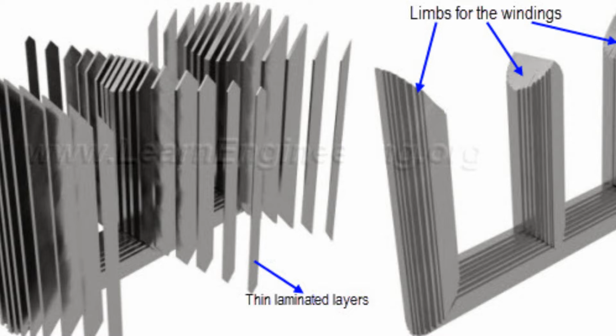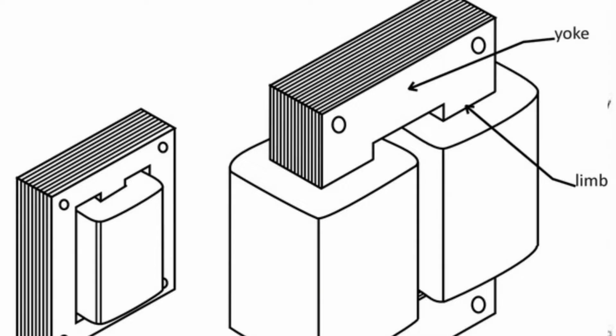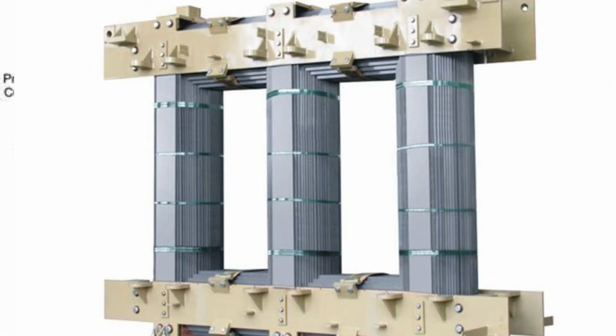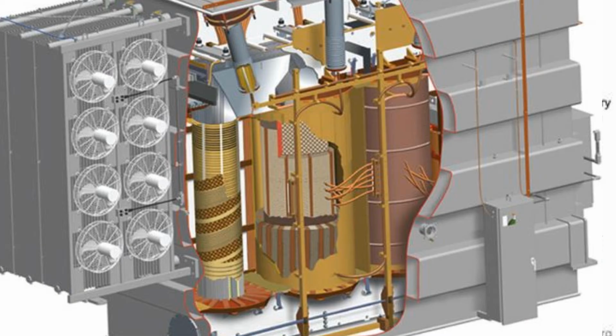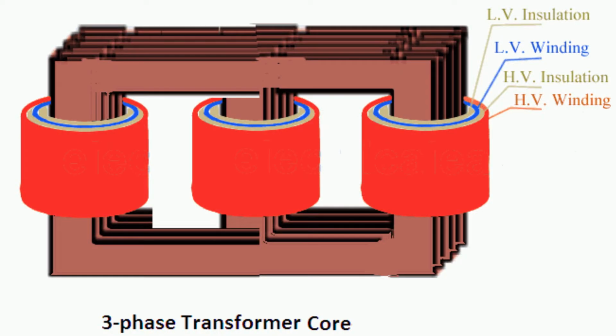The vertical sections of the core in which the windings are carried are referred to as the limbs, while the horizontal sections of the core that couple the limbs are referred to as yokes. The windings are made up of copper or aluminum conductor coil with a specific number of turns. Copper is the preferred material since it offers high electrical conductivity and high ductility. These properties reduce the amount of winding and make the material easier to wrap around the core.